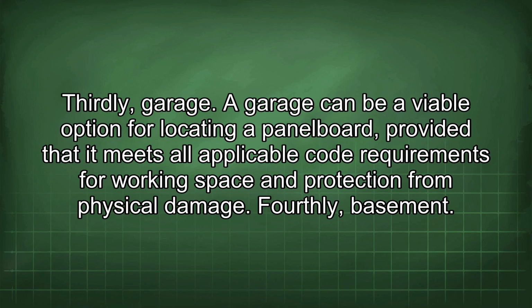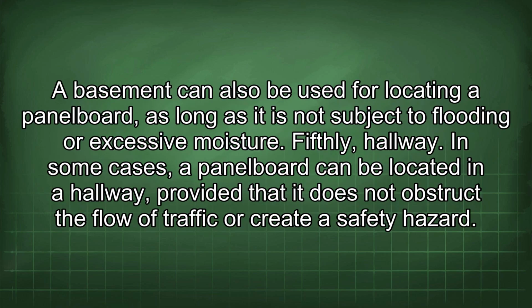Thirdly, a garage. A garage can be a viable option for locating a panel board, provided that it meets all applicable code requirements for working space and protection from physical damage. Fourthly, a basement. A basement can also be used for locating a panel board, as long as it is not subject to flooding or excessive moisture. Fifthly, a hallway. In some cases, a panel board can be located in a hallway, provided that it does not obstruct the flow of traffic or create a safety hazard.